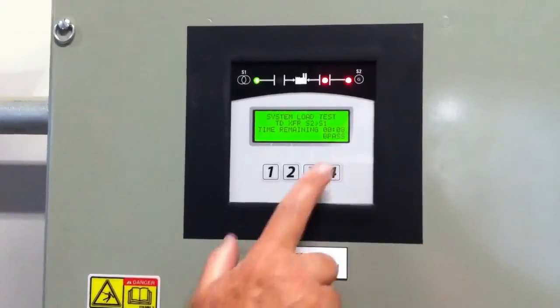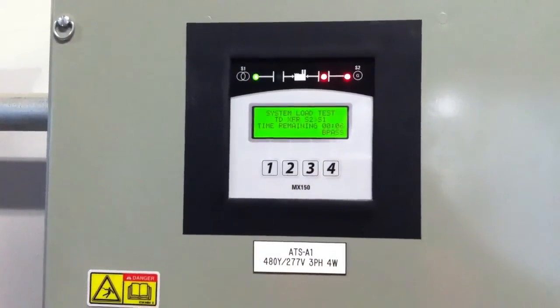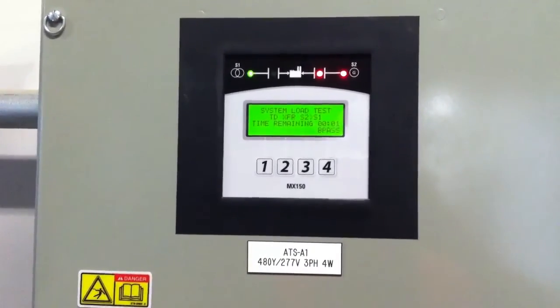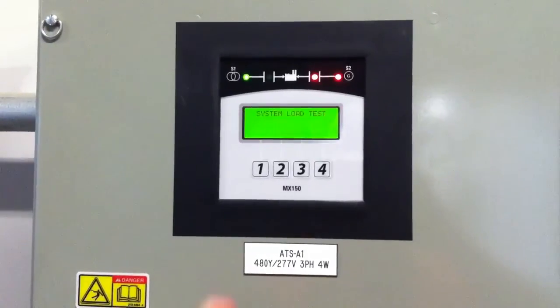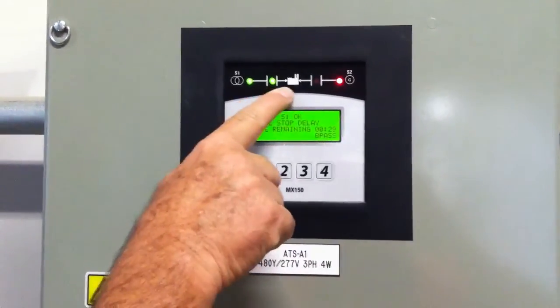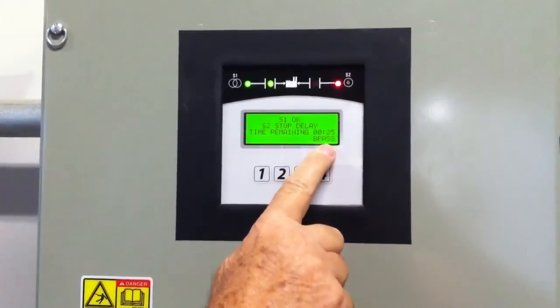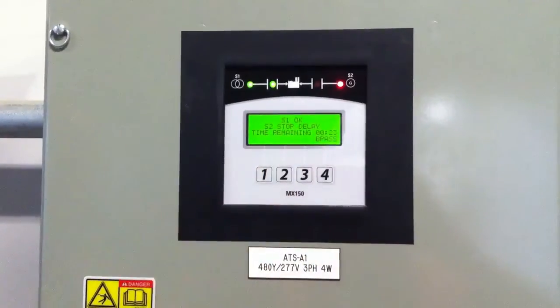So we go ahead there, we're timing down. Once we get to zero here, we're going to actually transfer back, and you'll hear the mechanism transfer. Now we're back. Utility's connected to the building again.